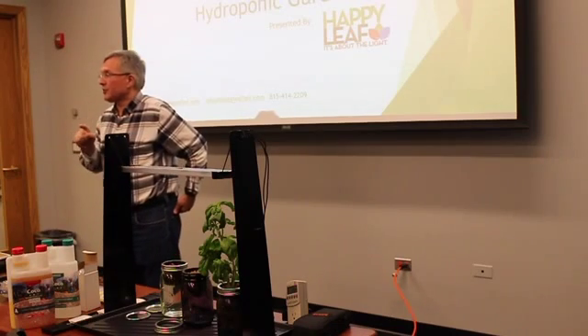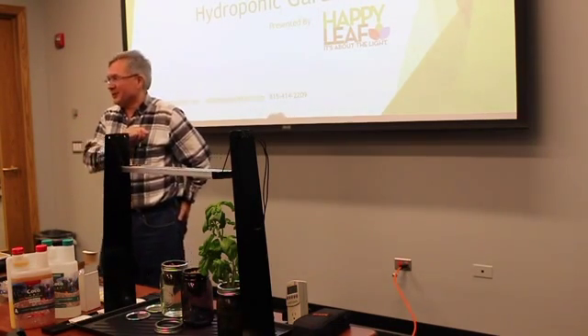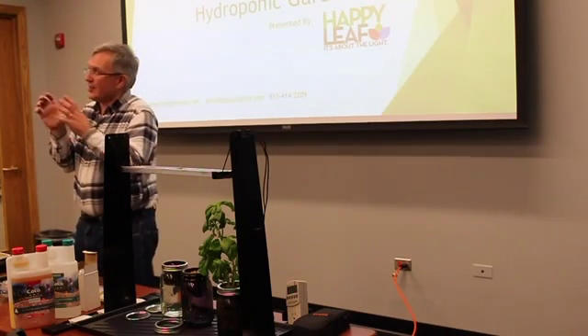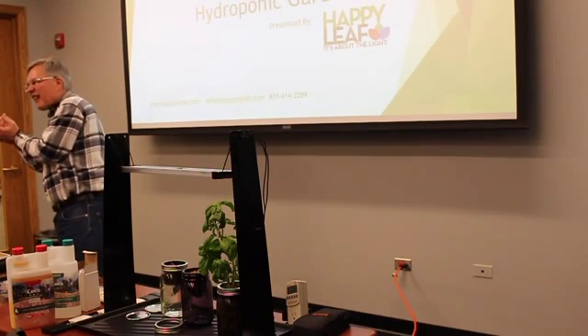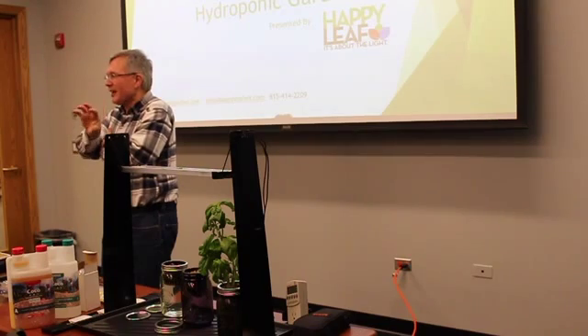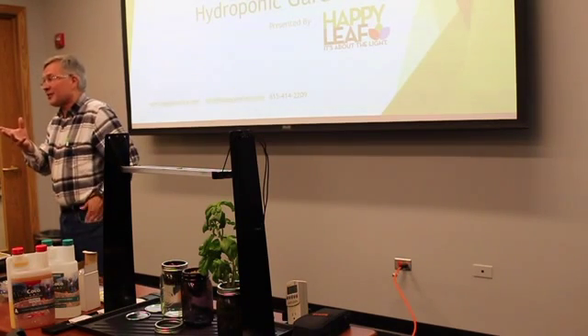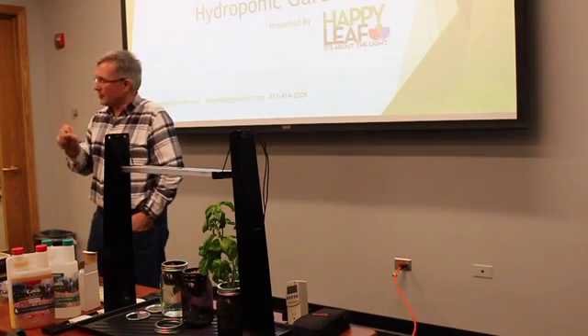Now, if you're burning electricity to heat your house, you already made a big mistake by using pure electricity. It's not a great way to do it. A heat pump is a good way to reduce that load. But what I'm saying is that 3 times benefit times 32% is about 95, 96% efficiency. So guess what? You've gotten the same total efficiency in your system as if you used that same natural gas and heated your house. So what I'm saying is natural gas is a really darn good way to heat your house if you have a good, efficient system.